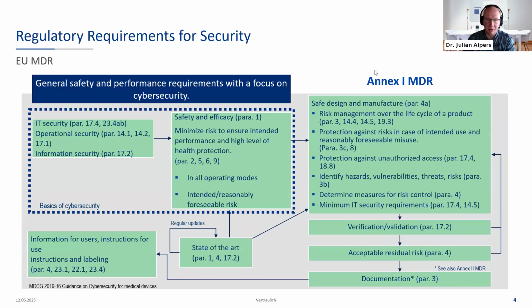Annex 1 in the MDR also covers specific parts for cybersecurity. We are obligated to have IT security, operational security, and information security, which is directly linked to safety and efficiency, because it aims to minimize risks, to ensure the intended performance, and to ensure a high level of health protection in all operating modes, as well as for everything regarding intended or reasonably foreseeable risk. And as per definition, an exploit of a vulnerability is always considered a reasonably foreseeable risk, not an unreasonable one.